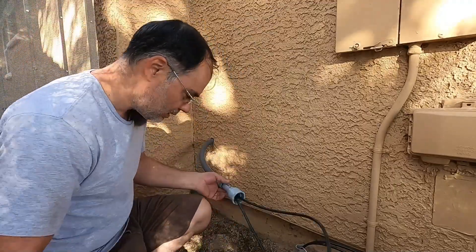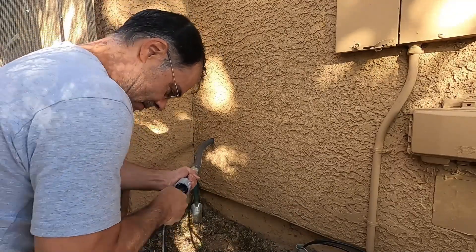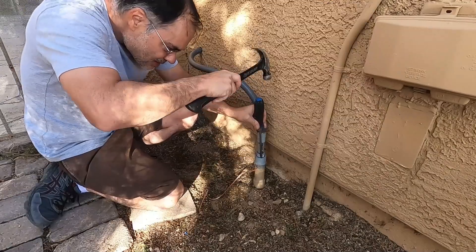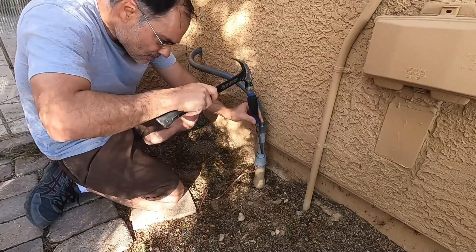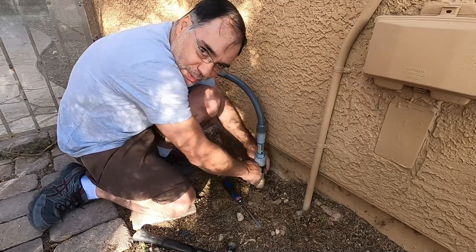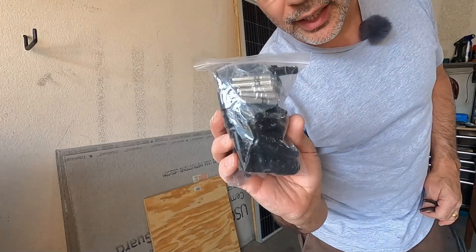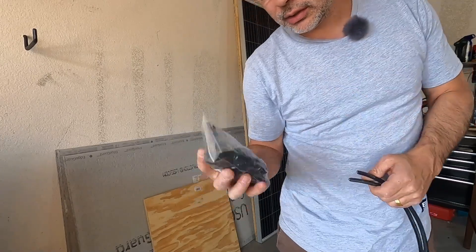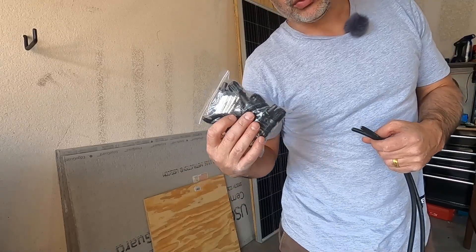I got my wife on the other end so it should be easier. Take our cables, feed them through here, then we'll feed them through our conduit into the garage. Now we're going to install some 8 gauge MC4 connectors. Make sure you use 8 gauge connectors with 8 gauge wire.